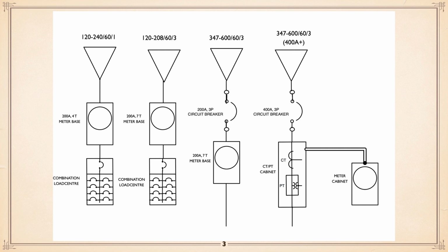So I call it combination because there is a main breaker for that load center, which also serves as the overcurrent protection for the whole system from there on, along with the individual breakers. So that's directly below the meter base. Now, the next one, 120/208 three-phase, very similar, except the fact that the meter base is different. Instead of a four terminal, see the 4T, it's seven terminal.